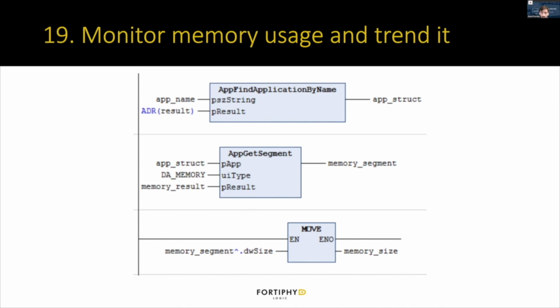For CODESYS, one way to do this is using the app get segment function block. This uses the CMP app library, so you have to first import that. Then you get the application by name, that handle, and use the app get segment function block to get information about the different memory segments within CODESYS. In this case, I'm using the DA memory segment and just getting the size from that using the move instruction. You can track that in the HMI and alert when that changes, to maybe indicate a change in the program.